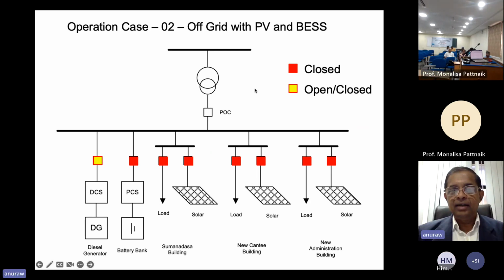This is a case where the grid is not available, off-grid operation with PV and battery energy storage. The diesel generator may or may not be in operation, depending on the battery's SOC level and the demand. If the demand can be met by the batteries, we use them first, because grid interruptions can be short-term.